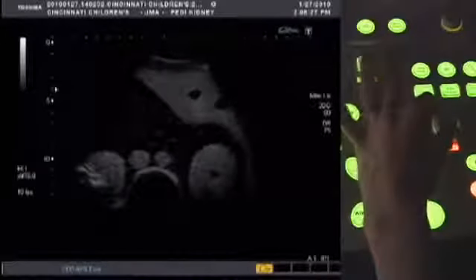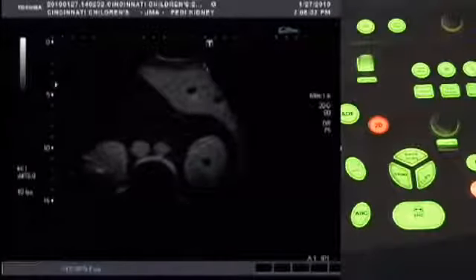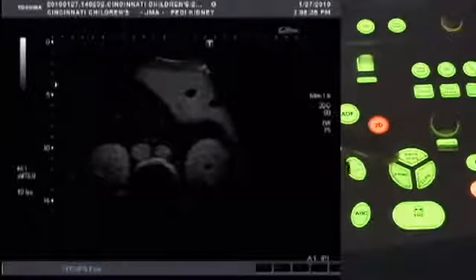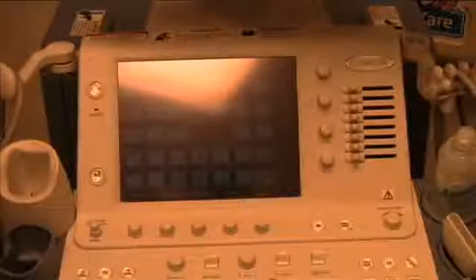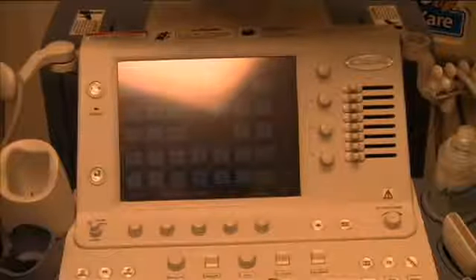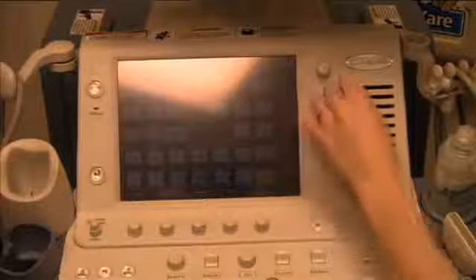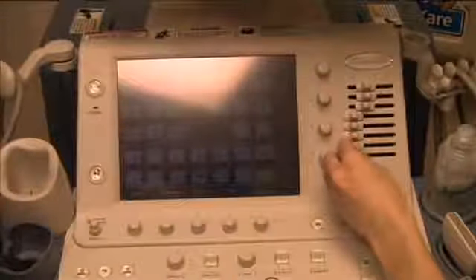Okay, now we'll zoom in just a little bit. Pressing Q scan will autofocus the image. Press that. Next, we're going to adjust the TGC, or time gain compensation. That's these dials right here that slide over. Sliding the top dials adjusts the superficial part of the image, and the bottom dials adjust the deeper part of the image.